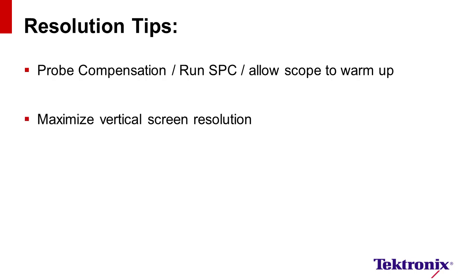Next, when a signal is displayed, make sure you're maximizing the displayed signal on screen. Doing so optimizes the signal coverage into the ADC and improves the number of used digitizing levels.